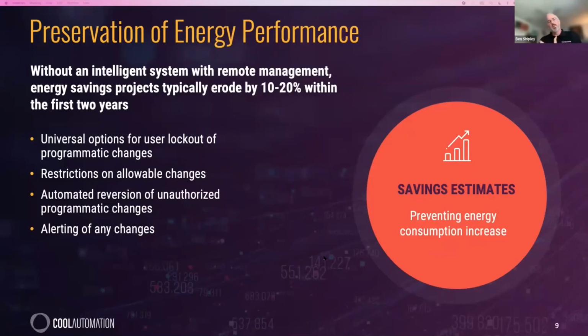So with the CoolAutomation platform, and really key to preserving these savings, the first one is the ability to universally lock out, no matter the manufacturer or the type of system, users and the changes that they can make locally at the site. Coupled with that, of course, is allowing them to also have limited adjustments, perhaps coupled with automated reversions, right? So based on occupancy transitions, being able to set back to the original set point settings.